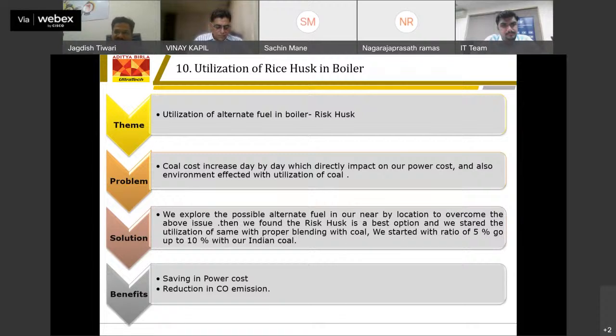And we have also, on the alternate fuel front, used rice husk in the boiler. Earlier, we were mixing the rice husk with coal and taking it into the bunker through coal, and we used about 5 to 10% in the previous year. This year, since we have linkage coal, our cost is less, and the rice husk cost is now higher, so we have stopped using rice husk in the boiler due to the high cost, and started using it in the cement plant.